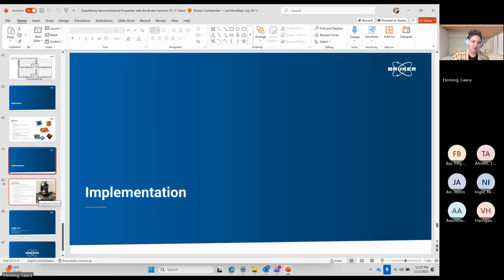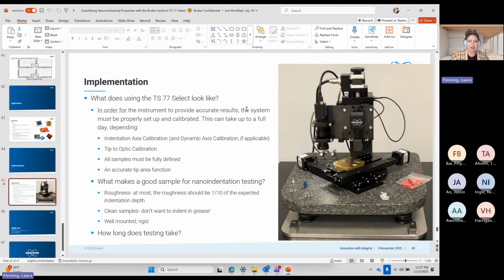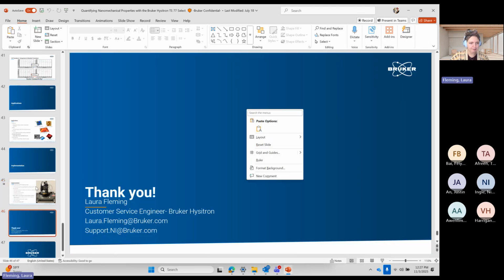Good question. So, implementation of testing. Oops, sorry, one slide too far. I like to answer this question before it gets asked: how long? You walk into an empty instrument and you have a sample in your hands. How long does it take you to get set up to make sure that you can test that sample successfully? The answer is anywhere between 2 hours and 8 hours, depending on how well the system is set up to begin with. For you, your system only has that one transducer. Many of my customers have more than one, so they're swapping transducers and probes all the time, which can make the setup take longer.